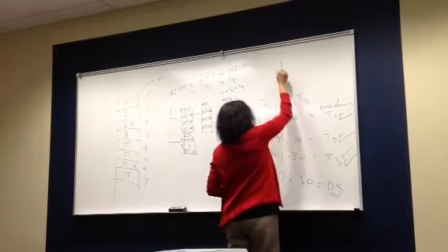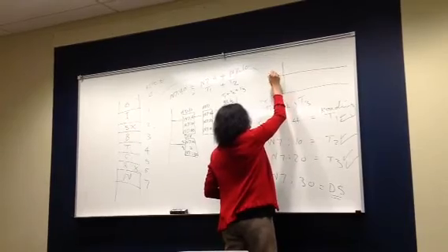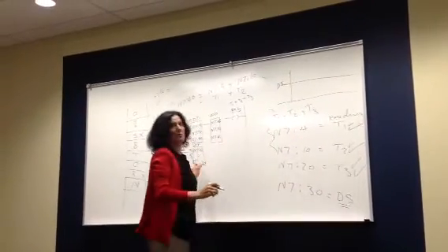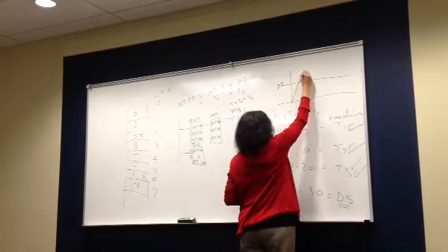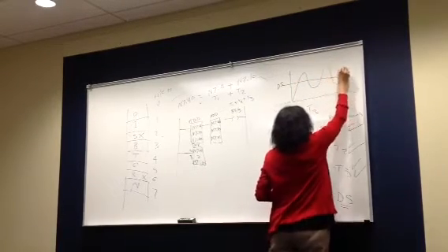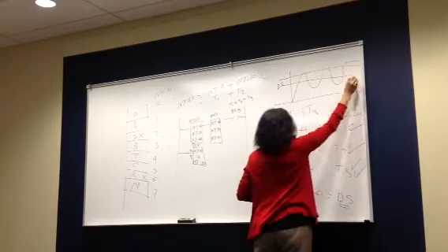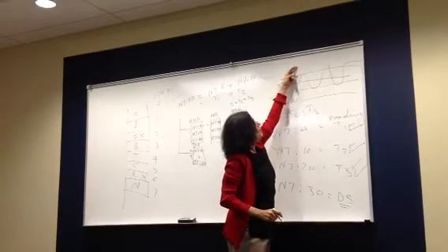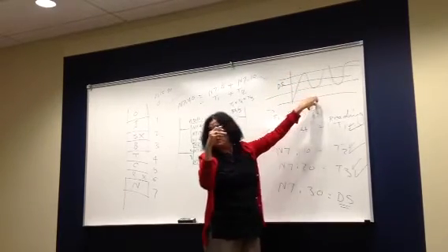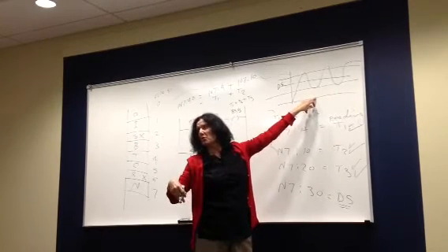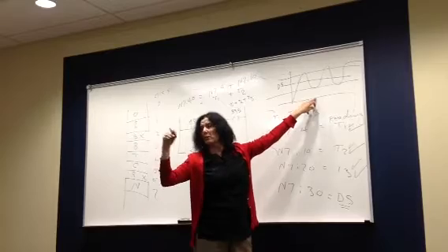I'll tell you quickly here, but I want to get into something. I have here the downstream water level, the one in here. Okay, and then I get the threshold here. I go between that. And I take every transmitter. If I am above or below, I eliminate it. I take the average on the other two, but that's going to take too long. So I take one by one and compare that.